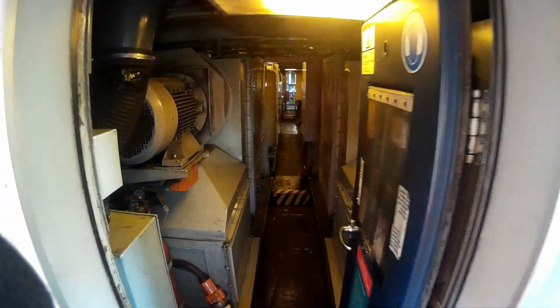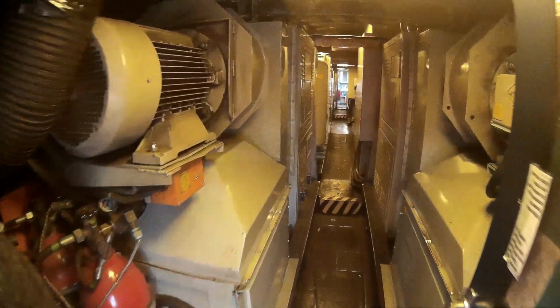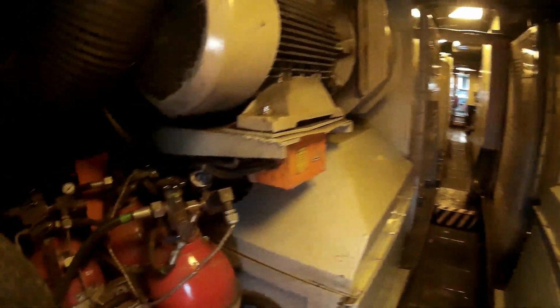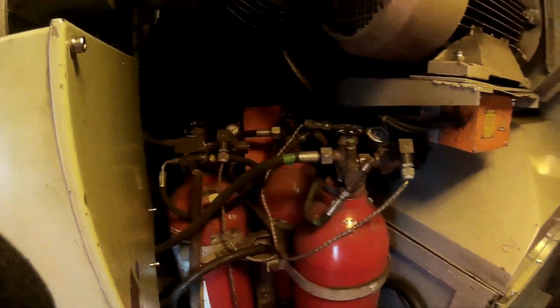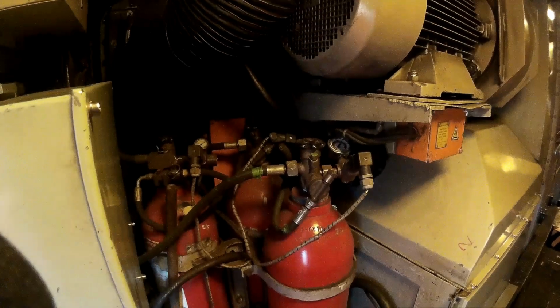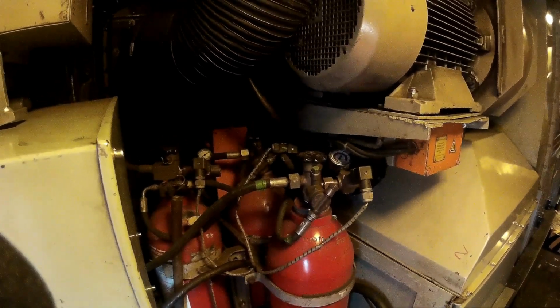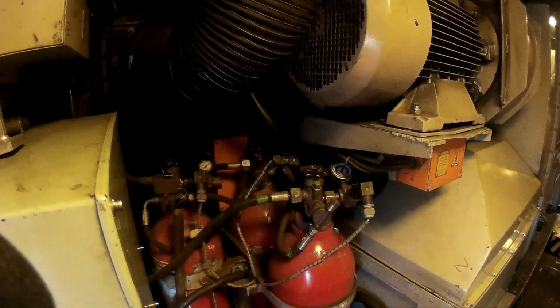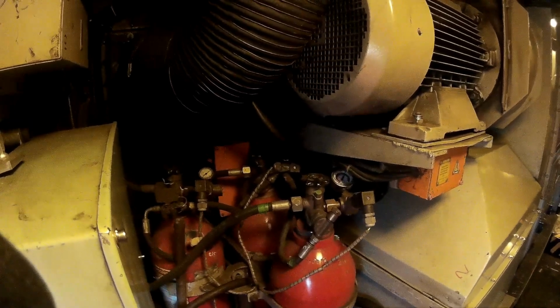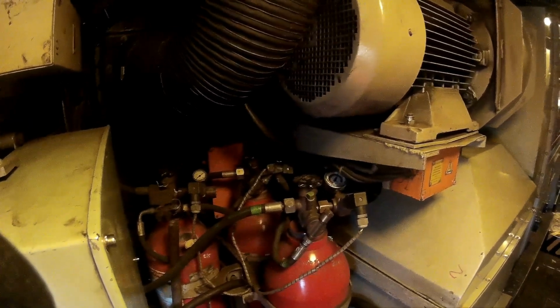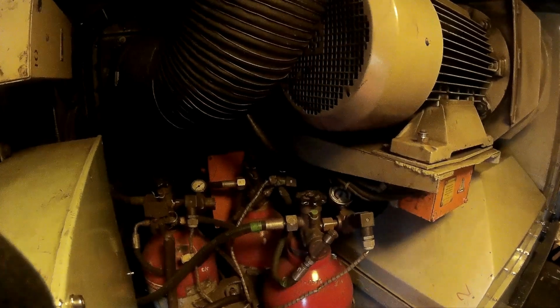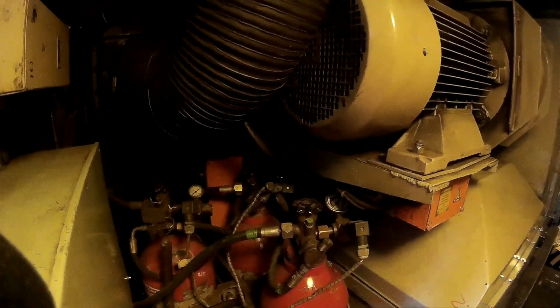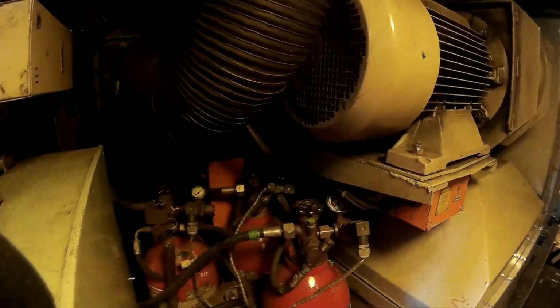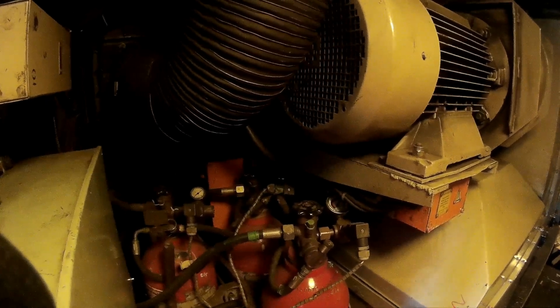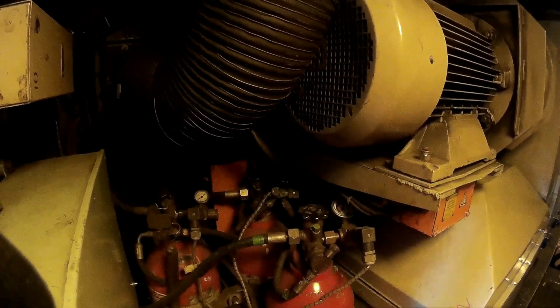As we go through the bulkhead door from number 1 cab into the equipment bay, the first thing we see on the left hand side is our fixed firefighting equipment, consisting of 3 Argonite bottles, pressurised between 150 and 220 bar, nominally 200 bar. If the locomotive detects a fire within the equipment bay, these automatically discharge and alert the driver via a fire alarm.